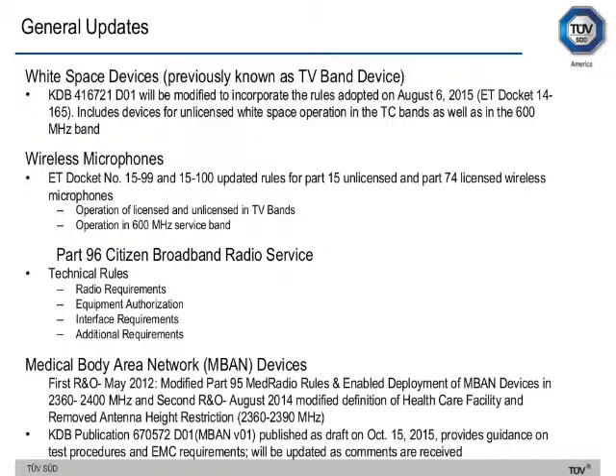For medical body area network devices and bands, a report and order was issued in May 2012 modifying Part 95 MedRadio rules and enabling deployment of MBAN devices in the 2360–2400 MHz range. A second report and order in August 2014 modified definitions of healthcare facility, removed antenna height restrictions, specifically for the 2360–2390 MHz band. KDB publication 670572D01 was published as draft on October 15, 2015, providing guidance on test procedures and EMC requirements, and is being updated as useful comments are received.